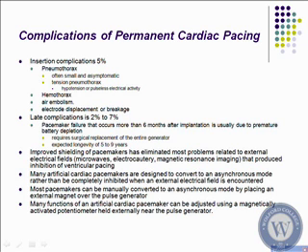Okay? So many artificial cardiac pacemakers are designed to convert to asynchronous mode when they're inhibited and the external field is encountered. That's why we put the magnet on. So it's basically going into a DOO. Okay, it's going to fire no matter what. Most pacemakers can usually be manually converted. Many functions of the artificial cardiac pacemaker can be adjusted using the magnetically activated potentiometer held externally near the pulse generator.